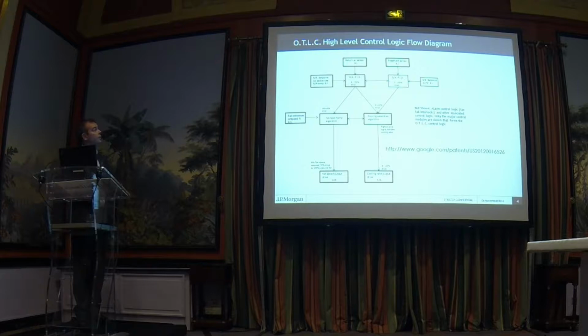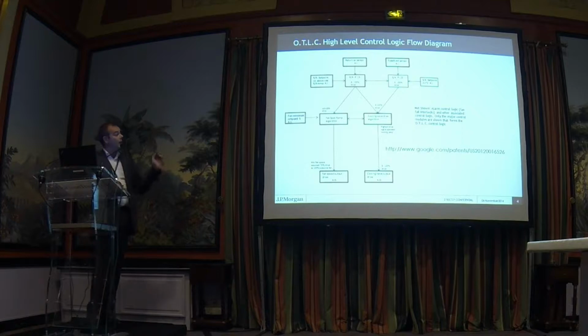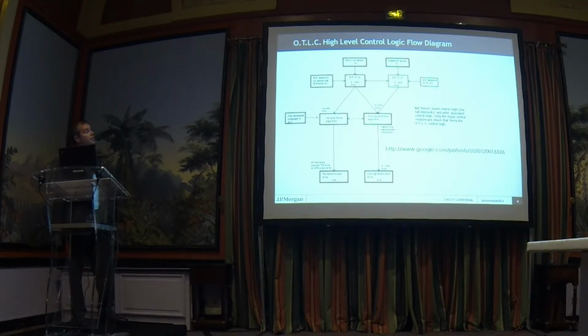So you've got return air and supply air, you've got 2 PID controls. Usually just this side here is all that happens inside a normal unit. So you've got the fan set point, minimum set point, fan ramp, and then the output to the fan and the output to the cooling valve. What I've done is I've basically made up an algorithm that combines both supply and return, combined it in this secret sauce algorithm I made up, and then basically worked out which one was more priority, and then that would control the valve.